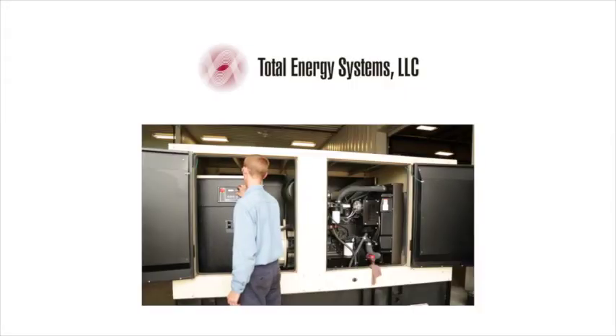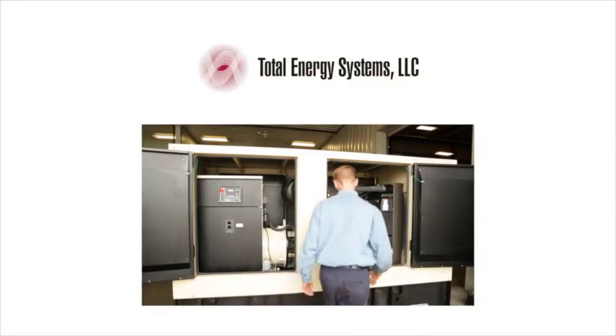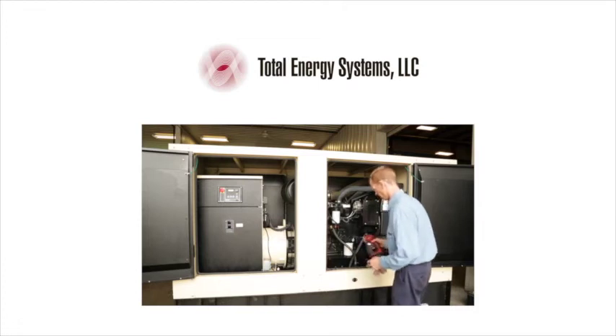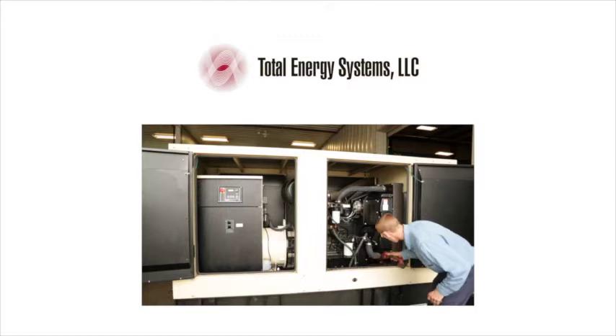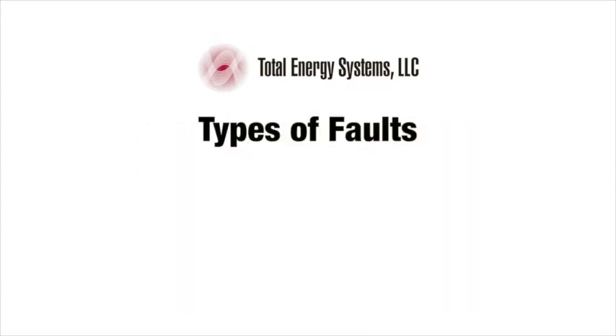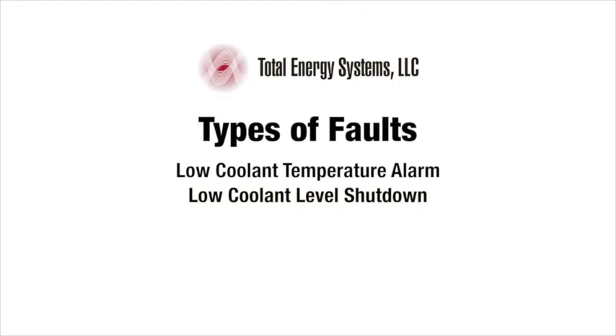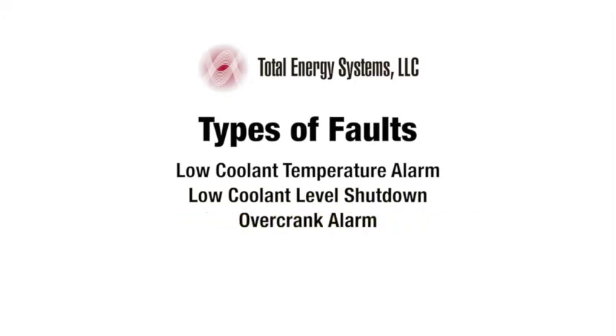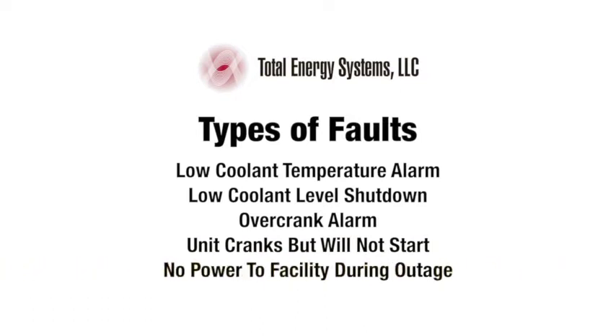This video covers faults on your generator that usually the generator system operator can review and correct before having to contact their generator service provider. The types of faults covered in this video that a system operator can check for are low coolant temperature alarm, low coolant level shutdown, overcrank alarm, the unit cranks but will not start, no power to the facility during a power outage, ATS fault alarm.